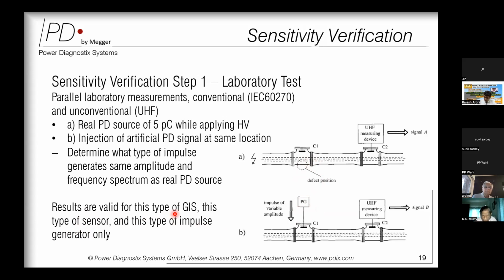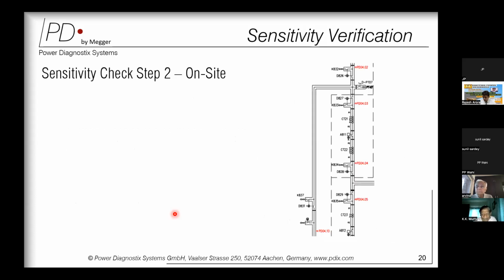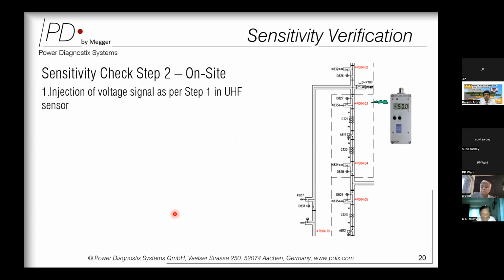Now we have the data in terms of a pulse which is equivalent to generating the 5 picocoulomb discharge. Step 2 is done on site. Once the GIS is shipped on site, it is assembled. We need to again perform the sensitivity check, to see whether my GIS is sensitive enough to react to a 5 picocoulomb partial discharge. The procedure is that we carry the same pulse injector on site and inject the same voltage pulse into a particular sensor.